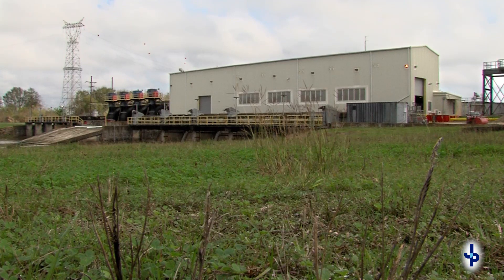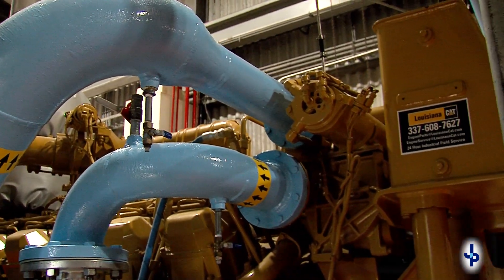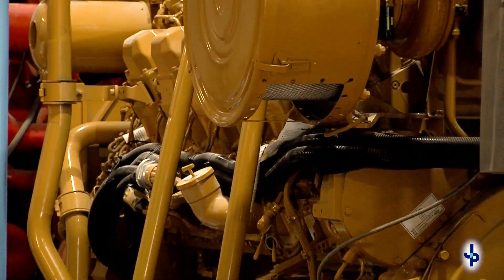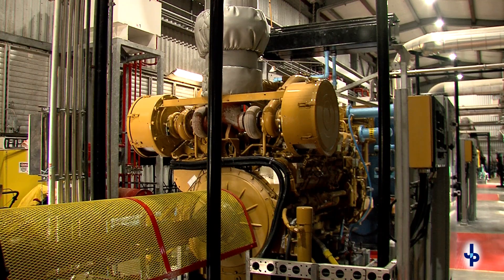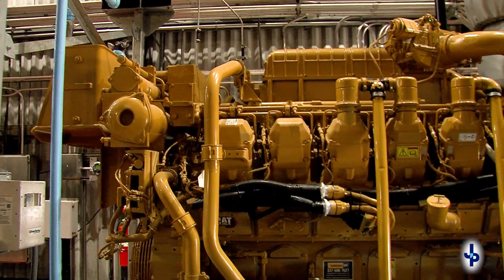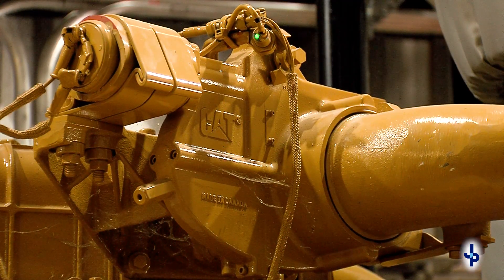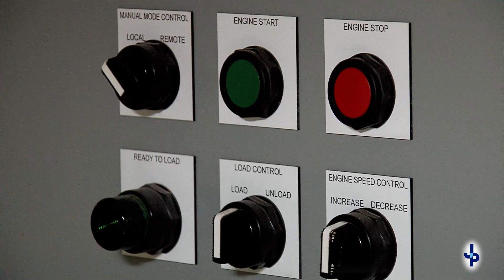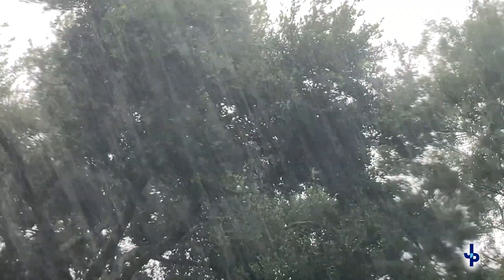Here at the Planters Pump Station, drainage has recently completed a $2 million facility upgrade, which replaces two diesel engines and pump controllers. The diesel engines are the drive or power source for the pumps. This project helps maintain reliability at pump stations by proactively replacing antiquated equipment. With updated controllers, the station has the ability to be automated, which improves our operational efficiency and response time during rain events.